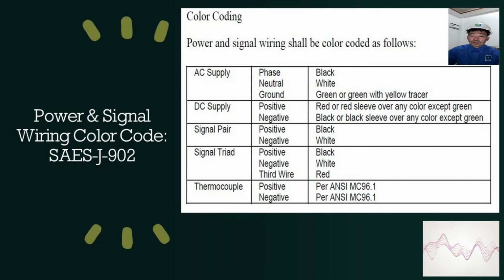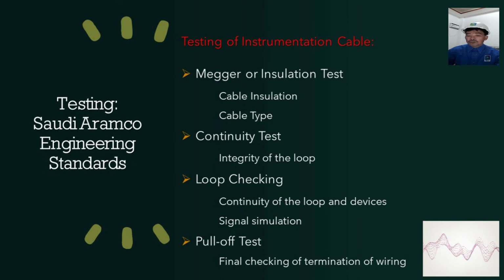So gentlemen, you should know this color coding because this is very important. So, testing of instrument cable. Of course, instrument cable will be subject to megger or insulation tests, depending on cable insulation and cable type. Of course, we're gonna do continuity tests to check the integrity of the loop or the circuit, and we have the loop checking as well, continuity of the loop and devices, and we're gonna do the signal simulation, including the process controller. We have also pull-off tests, final checking of termination of wiring.